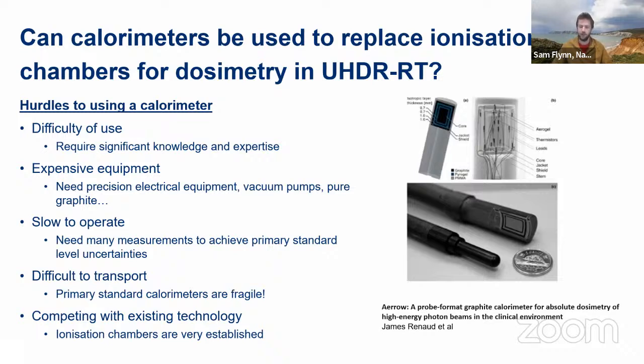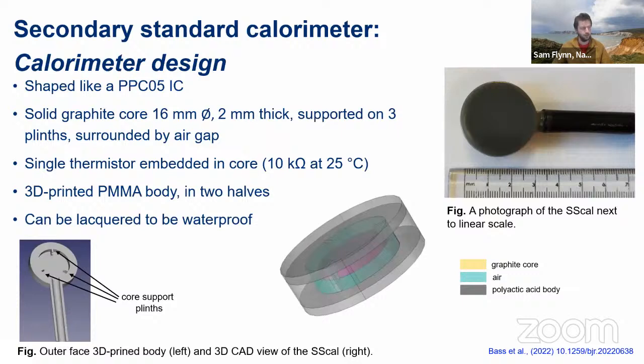And that was our initial approach. Next I'm going to present how simple you can make a calorimeter and still have it be useful for a clinical measurement. So this is it. This is our secondary standard calorimeter. The active volume of it is just a simple graphite core. It's 16 millimeter diameter, 2 millimeters thick, with a single thermistor in it. We're not using aerogel or anything to thermally isolate it, we're just using air, and it's made out of a 3D printed case, PMMA in 2 halves. You stick them together, you lacquer it to make it waterproof, and then it's done.